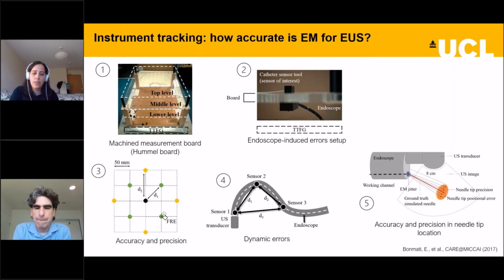We also included a simple experiment to evaluate the dynamic errors by fixing the endoscope in a way such that 3 of the sensors would form a triangle. And then we quantified the differences between the edges of this triangle while the endoscope was moving. Finally, we also wanted to know how precisely we would be able to estimate the tip of a needle if the sensor was placed at the end of the working channel of the endoscope.